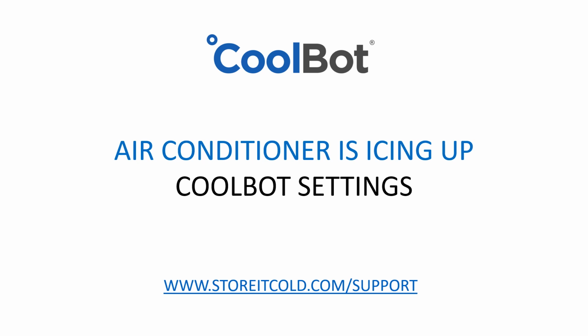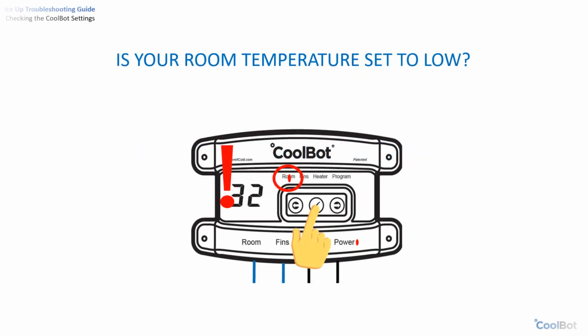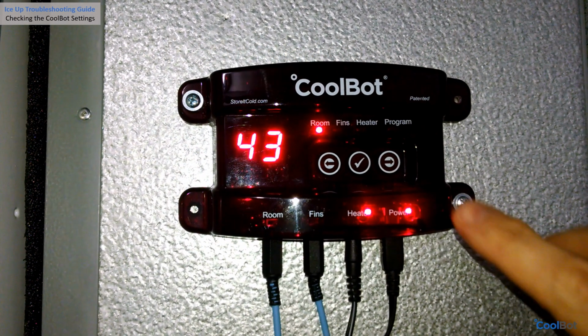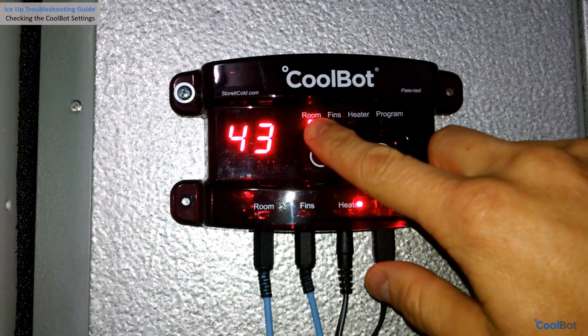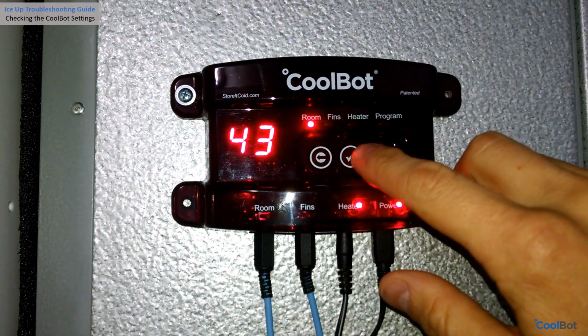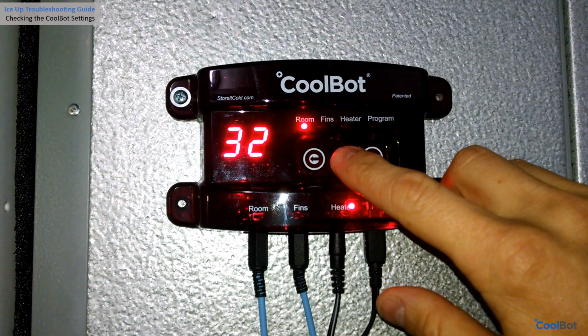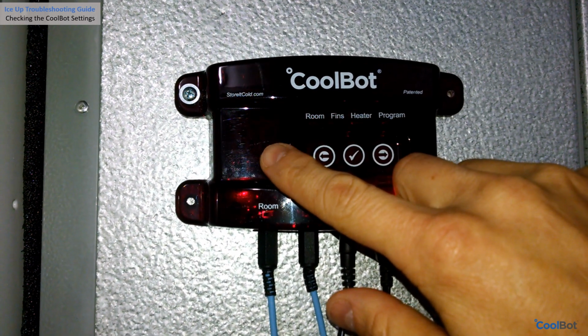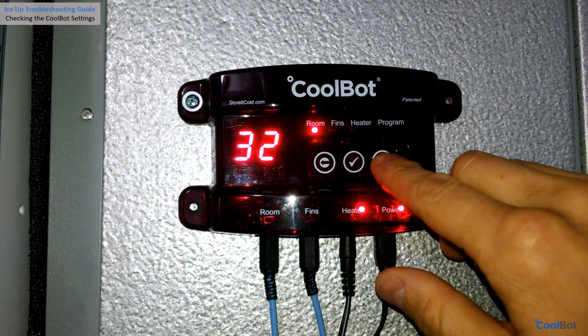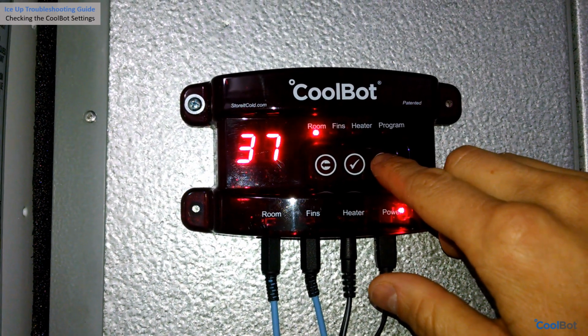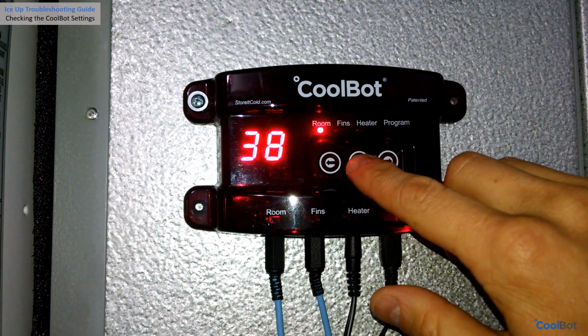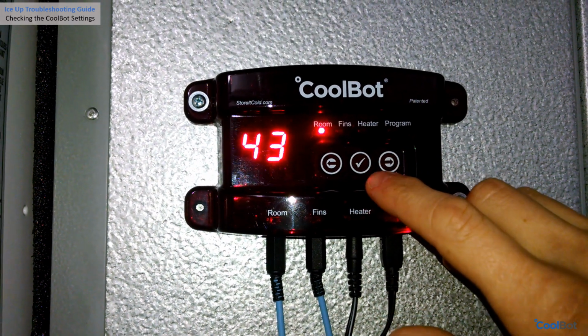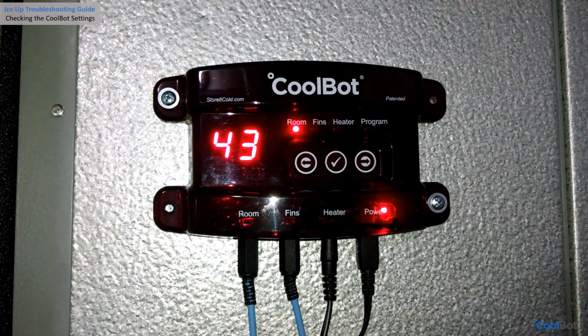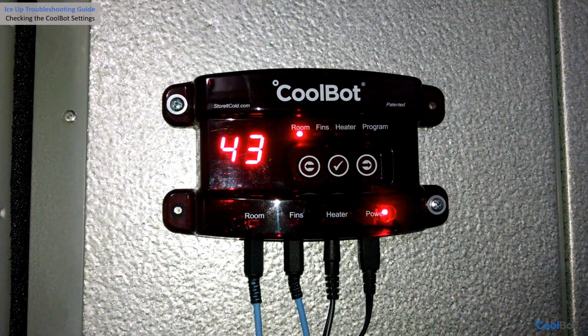Now that we have checked the CoolBot sensors and heater cable, let's take a look at the settings of the CoolBot and make sure that everything is set up correctly. Is the temperature set too low? Make sure the indicator light is on the room position. Press the checkmark button. The current set temperature will blink on the display. Adjust with the arrows if necessary to the desired value. Press the check mark to save. Your CoolBot will go back to display the current room temperature.